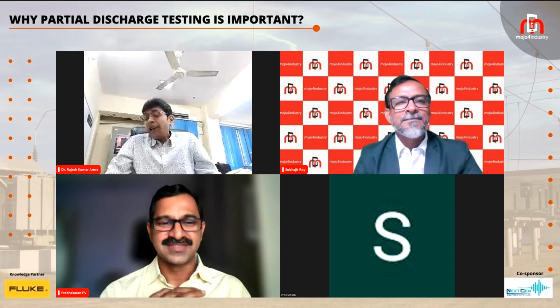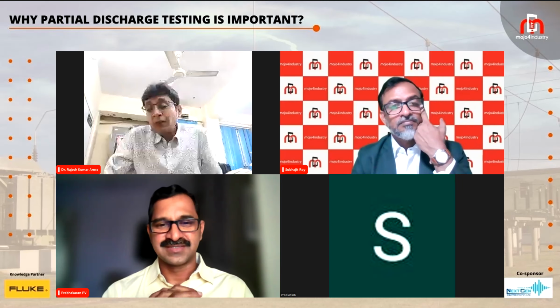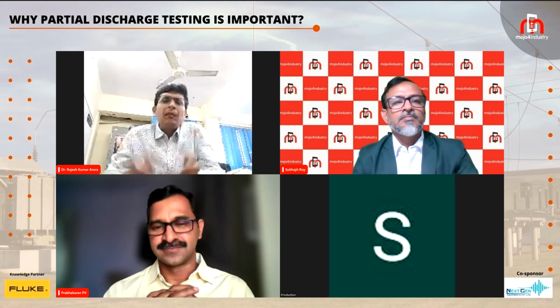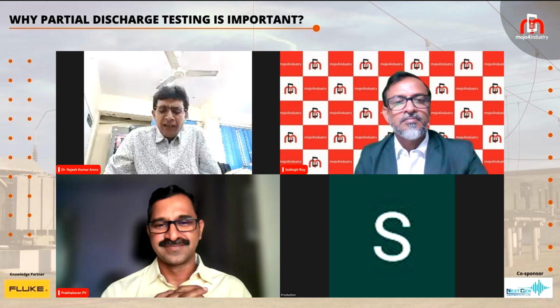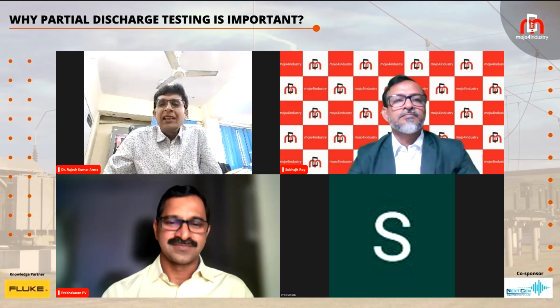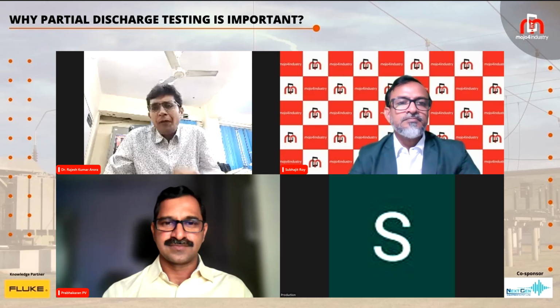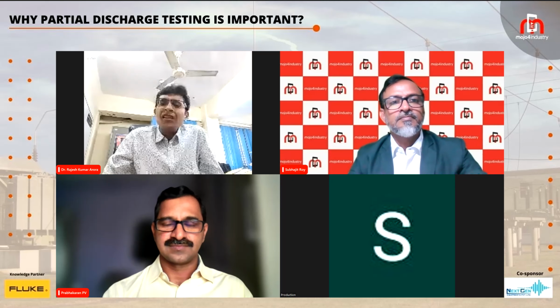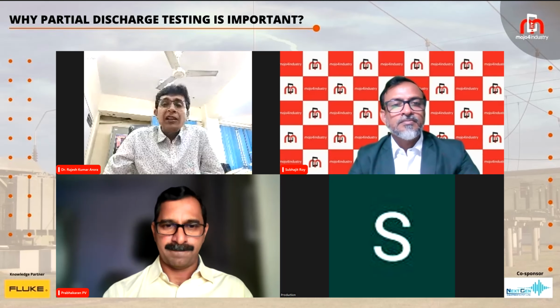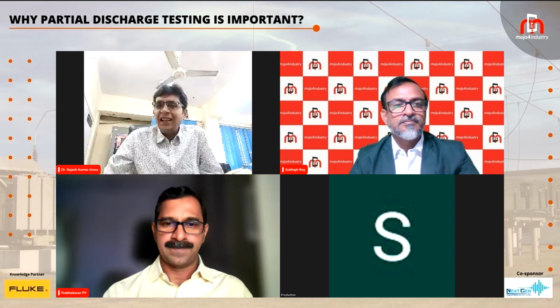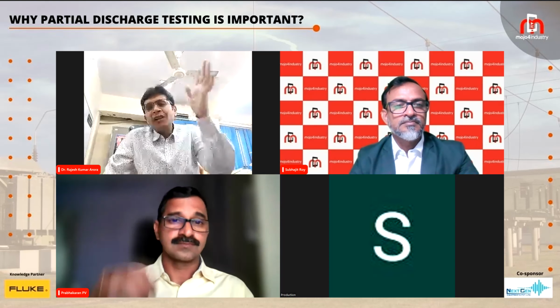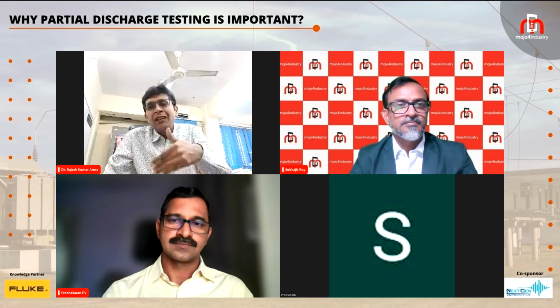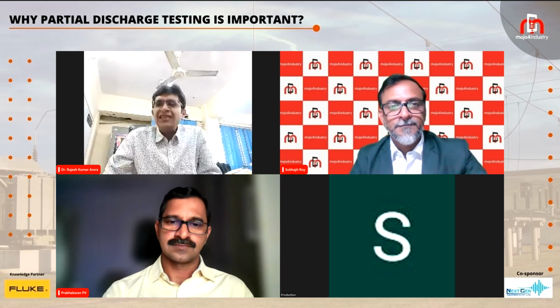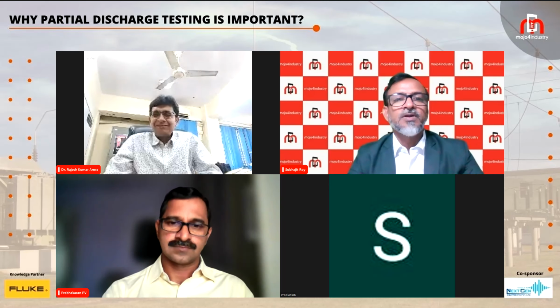Yes sir, infrared camera versus partial discharge: there is a major difference. In simple words, an infrared camera basically detects heat, and that heat is because of loose connections and the flow of heavy current. Whereas partial discharge is linked directly to dielectric weakness, dielectric impurity, dielectric integrity. One works for current and loose connection, the other works for impurity in the insulation. It's a major difference.